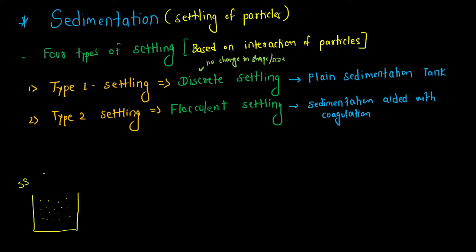Smaller than suspended solids, we have colloidal solids and dissolved solids. To remove these, the particle size is very, very small. So what we do is add some chemicals in the liquid so that these small particles stick to each other. The larger suspended particles have certain weight, so they settle easily at the bottom. But colloidal solids and dissolved solids have very little weight and will take a very long time to settle, or may not settle at all — they will keep on remaining in suspension.